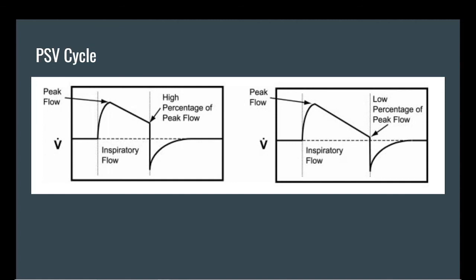The algorithms used to cycle PSV breaths have traditionally been fixed at a certain percentage of peak inspiratory flow, meaning that when the patient's inspiratory flow decreases to a predetermined level, classically 25%, the breath cycle would move into exhalation. And we can see that here. And then the 10% versus the 40%.